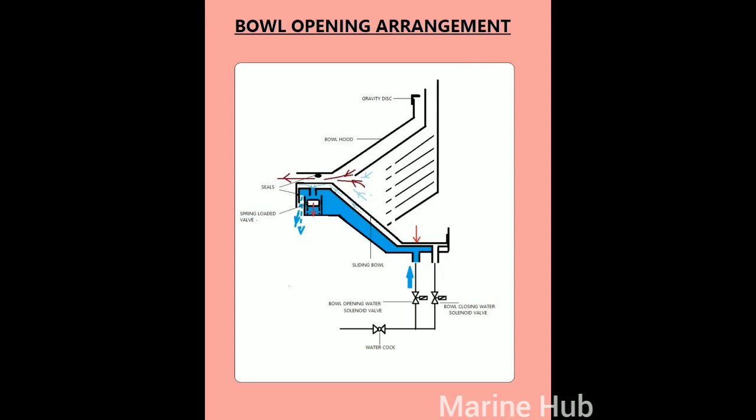Then the water will press the spring-loaded valve and let the water in the closing water chamber drain. Then the bowl will open and all the sludge will be discharged to prepare the bowl for a new cycle.